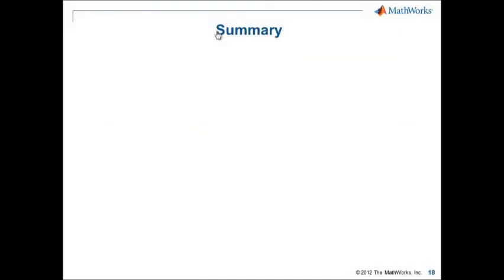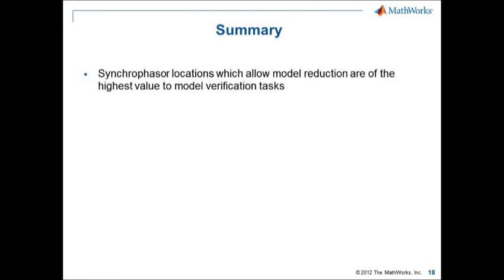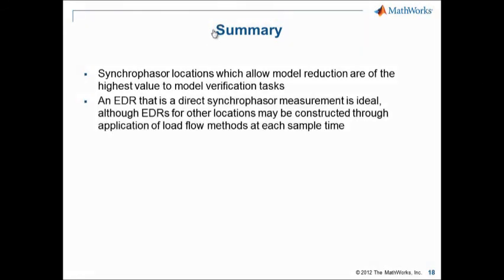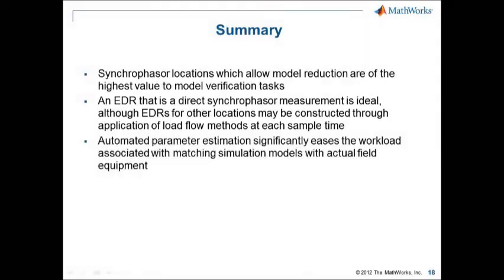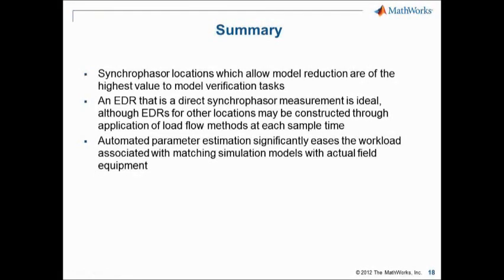And in summary, I would like to emphasize the key points that we saw in this presentation. First, the synchrophasor locations that allow model reduction are of the highest value for these model verification tasks. Secondly, an enforced dynamic response that is a direct synchrophasor measurement, like the one we saw at the point of connection, would be ideal. But if you don't have those ideal PMU locations, you can construct a PQV profile and then bring that as an enforced dynamic response in your simulation. And finally, the automated parameter estimation task that we saw can help you significantly reduce the workload associated with matching the simulation models with actual field equipment.